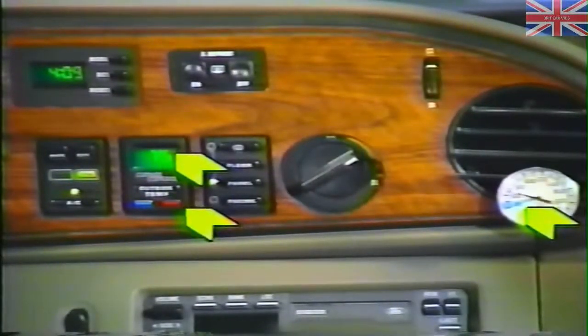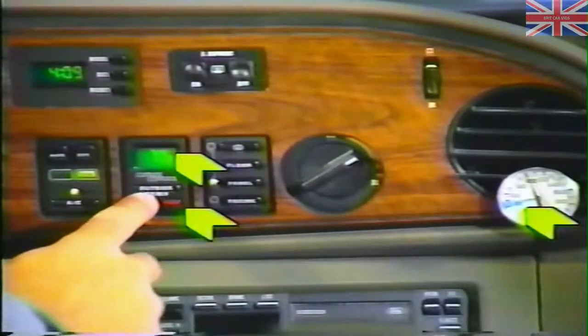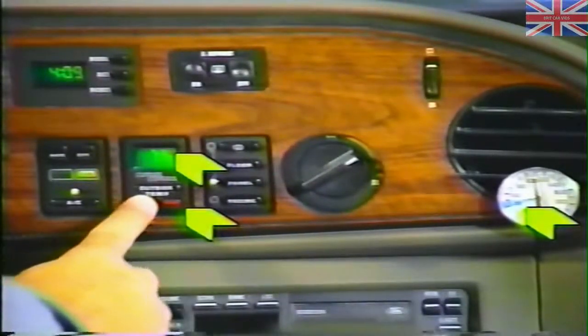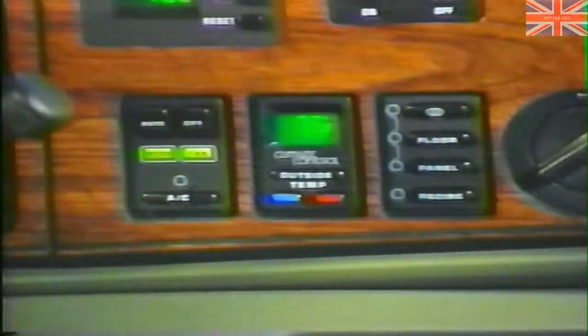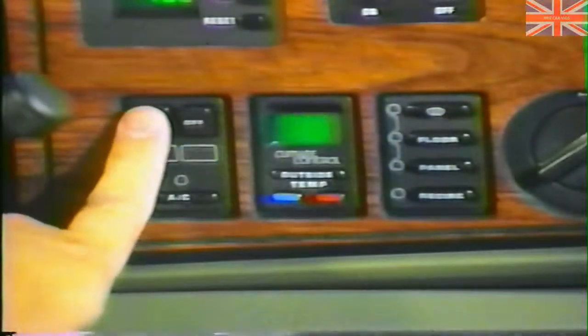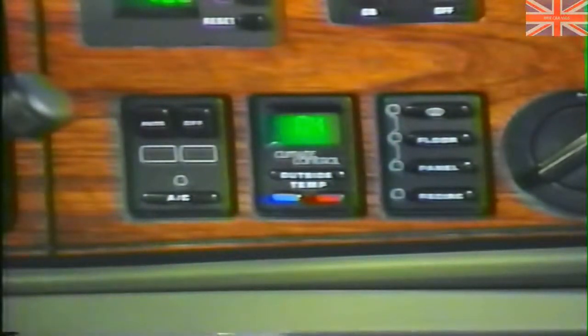Pressing the warm button will exit self-diagnostics and clear codes automatically once the malfunctioning component has been repaired. In fact, this system does not really retain codes in memory. As you enter self-diagnostics, the entire system goes through a self-test, activating and checking resistances on each component in the system.